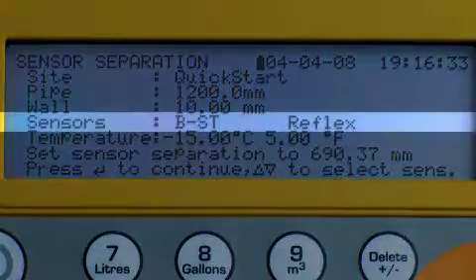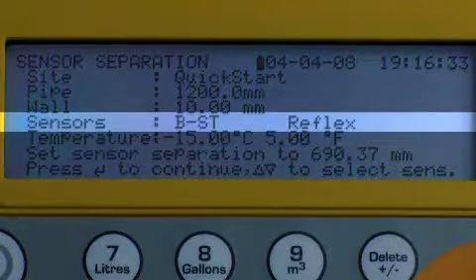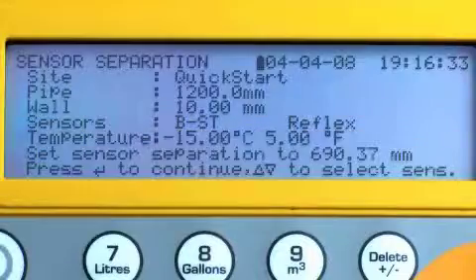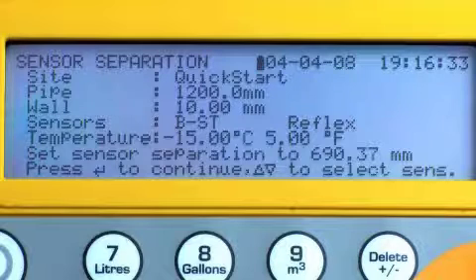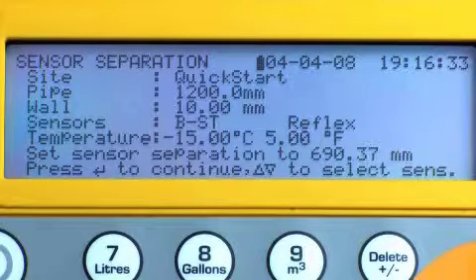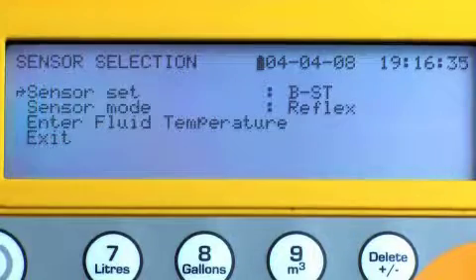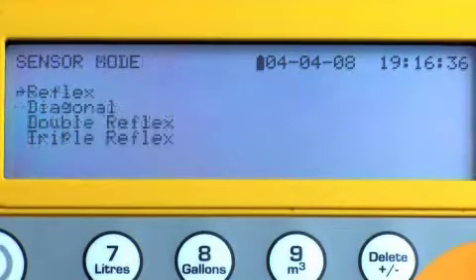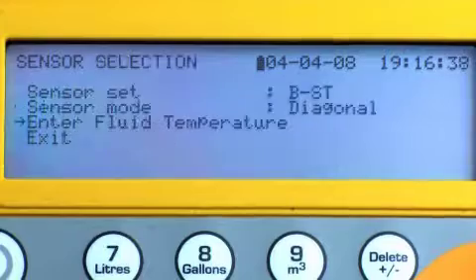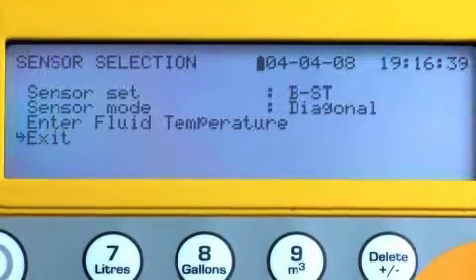The mode of operation just demonstrated is called reflex mode. On large pipes and potentially difficult applications, we may need to set up the sensors in diagonal mode to improve signal levels. For diagonal mode operation, press scroll and select sensor mode, press enter and select diagonal mode, scroll down to exit and press enter.